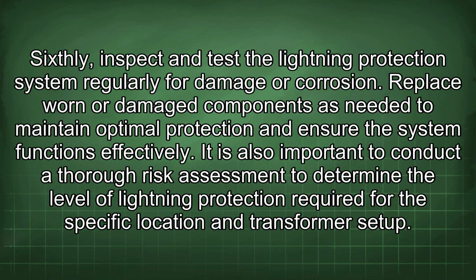Sixthly, inspect and test the lightning protection system regularly for damage or corrosion. Replace worn or damaged components as needed to maintain optimal protection and ensure the system functions effectively. It is also important to conduct a thorough risk assessment to determine the level of lightning protection required for the specific location and transformer setup.